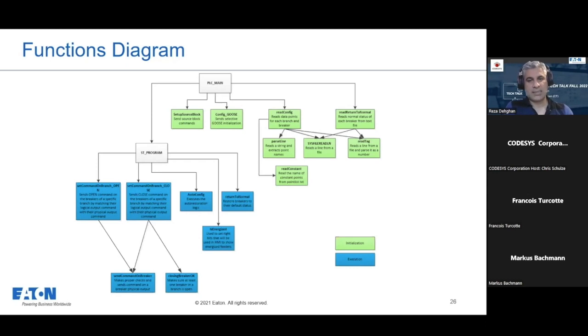And once the initialization is done, we just start looping around this ST program. That ST program has different modules to execute return to normal, to execute the automatic restoration, and to loop through the status of the system to see if we received any commands, either from the relays in the form of protection done that triggers their logic for restoration, or in the form of a command from a user through the HMI. So all the blue boxes are the execution or runtime modules, and everything in green is the initialization phase. Next page.